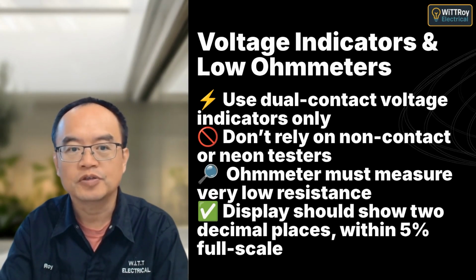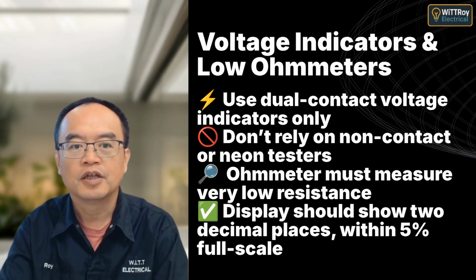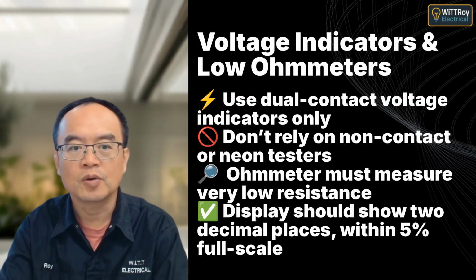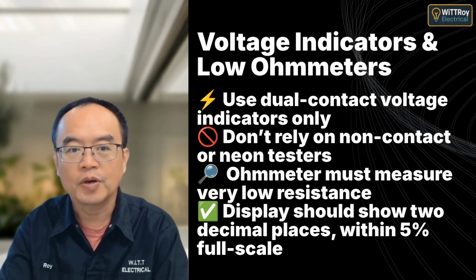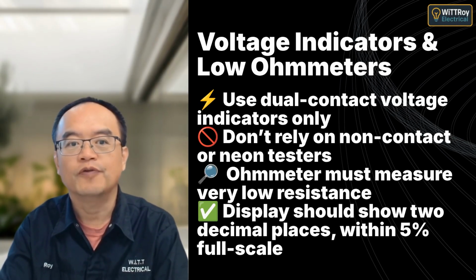Use a dual contact voltage indicator to confirm isolation. For low resistance testing, use a low range ohm meter that can measure small values accurately with 2 decimal places, within 5% error.